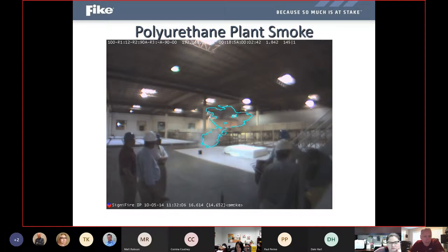The advantage is, again, when you've got high ceilings, you can see that smoke still has not made it up to the ceiling. So traditional spot type smoke detectors or beam detectors up at the ceiling would not have gone into alarm. But with our camera system, it's detecting it at the floor and it doesn't wait for that smoke to get to a certain elevation or high enough up before it goes into alarm. So it can detect things before there would be enough time for the smoke to actually go to the detector. It takes the detection to the smoke and to the fire.